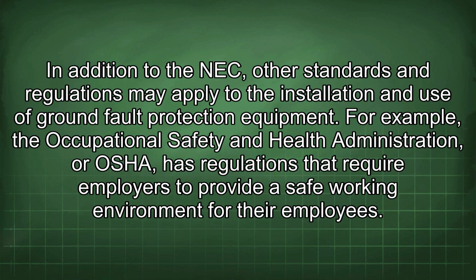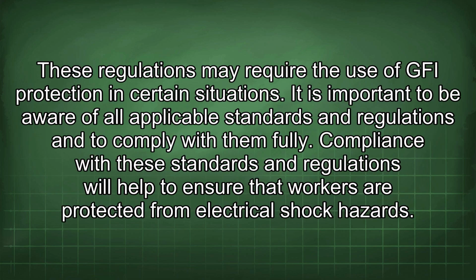In addition to the NEC, other standards and regulations may apply to the installation and use of ground fault protection equipment. For example, the Occupational Safety and Health Administration, or OSHA, has regulations that require employers to provide a safe working environment for their employees. These regulations may require the use of GFI protection in certain situations. It is important to be aware of all applicable standards and regulations and to comply with them fully. Compliance with these standards and regulations will help to ensure that workers are protected from electrical shock hazards.